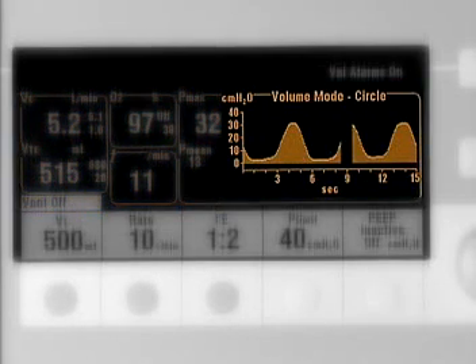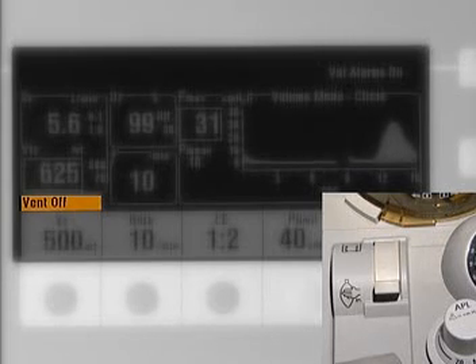In the bag mode, a message alerts the operator that the ventilator is not activated. Digital volume, O2, and airway pressure monitoring is active in the bag mode. There is an airway pressure waveform as well. A single step is required to move from manual to mechanical ventilation. The bag to vent switch is located on the top of the breathing system. Vent on displays on the ventilator screen.